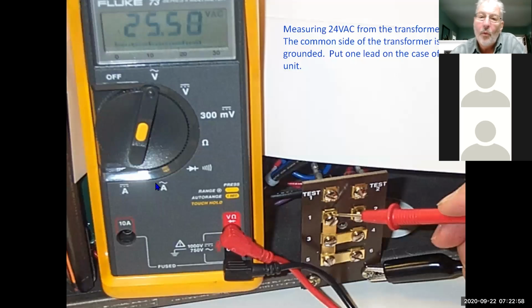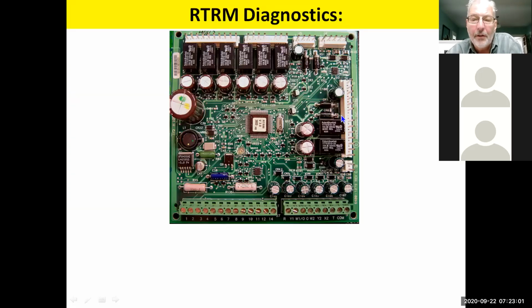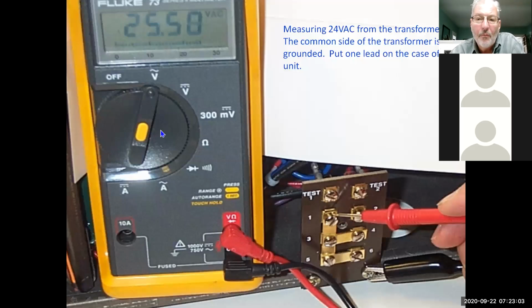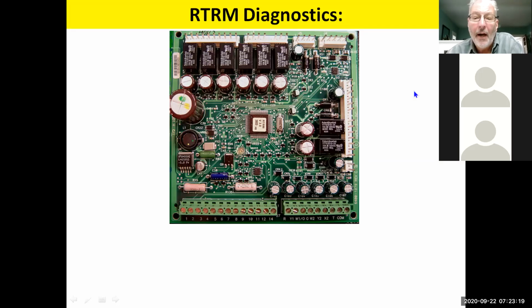All right, so with that being said, there are some things we need to look for when we're checking voltages on the system. Again, there should be 24 volts on this connector right here. So you can always go from here to ground, and there should be 24 volts there on the old unit as well as the new unit. Okay. On the RTRM board, there's also some diagnostics built in. So we've got all of our communication. We've got our plugs.